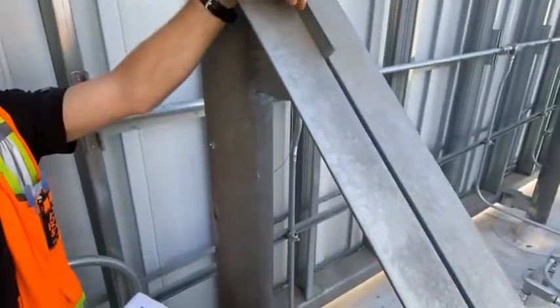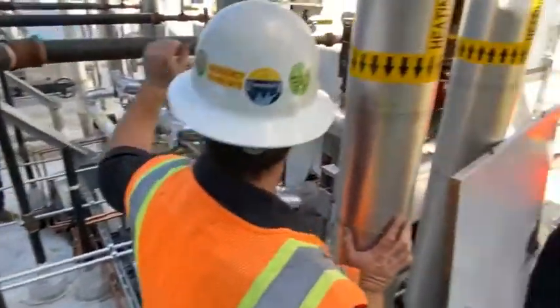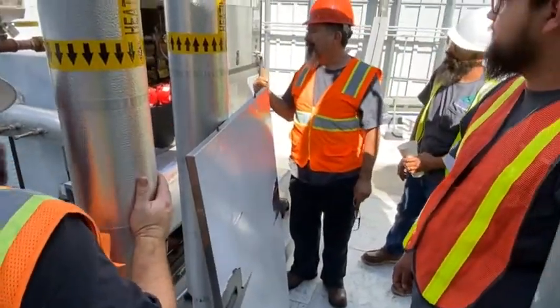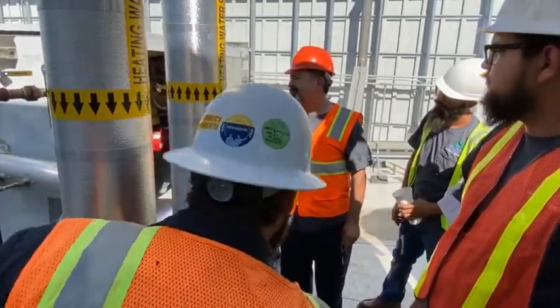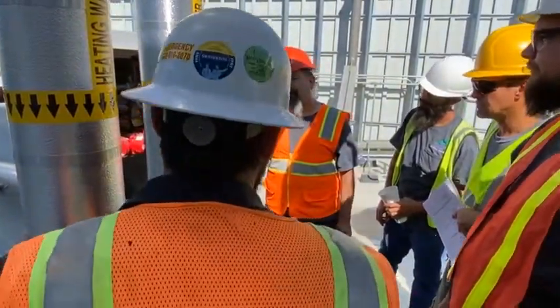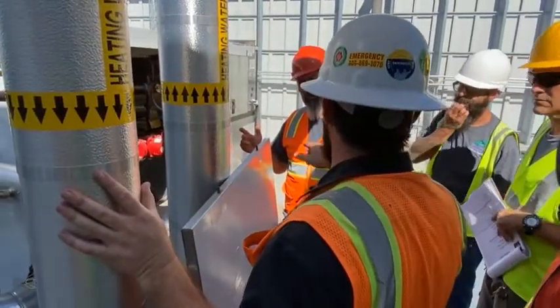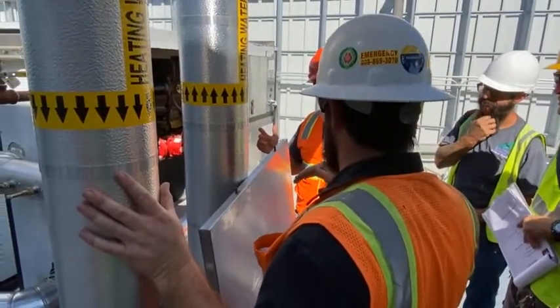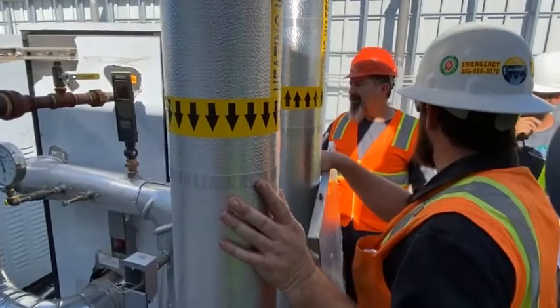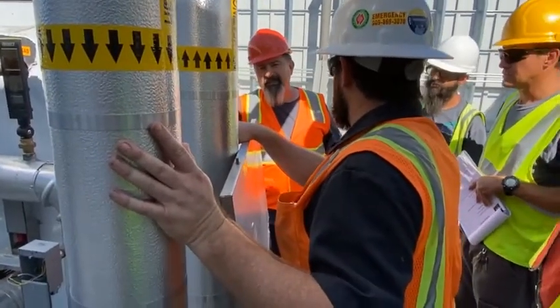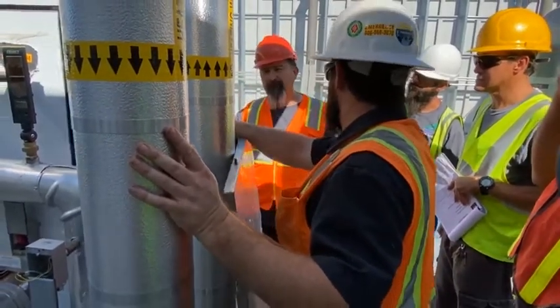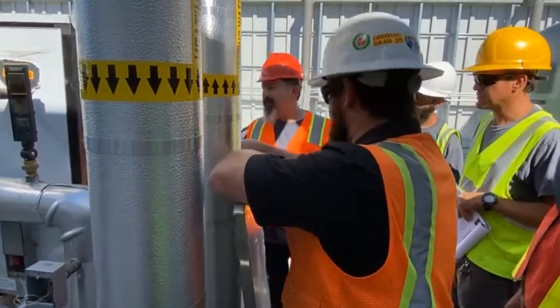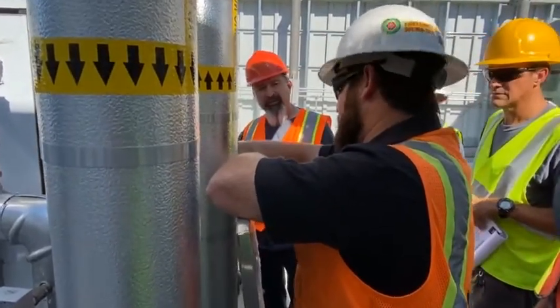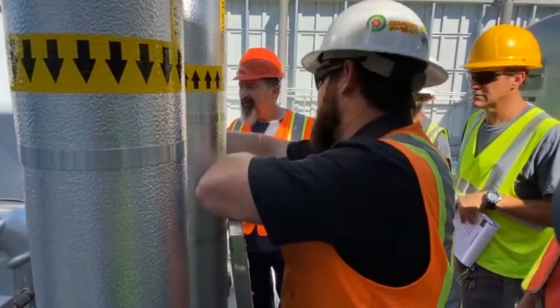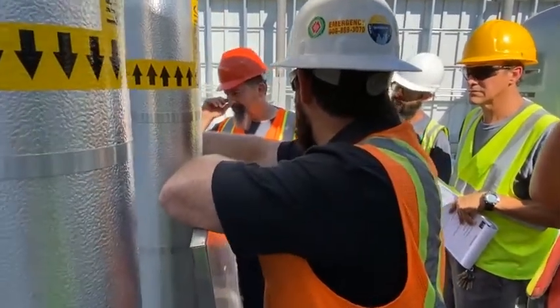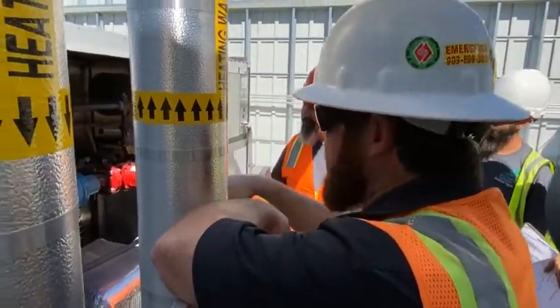So this three-way valve between the in and the out, what's its purpose? It's to preheat the water going into the water heater or the boiler to make it above condensing temperature. It opens and closes based on temperature. If the water coming on the inlet is too cold, it'll pull from the outlet to warm that water up so it doesn't condense.